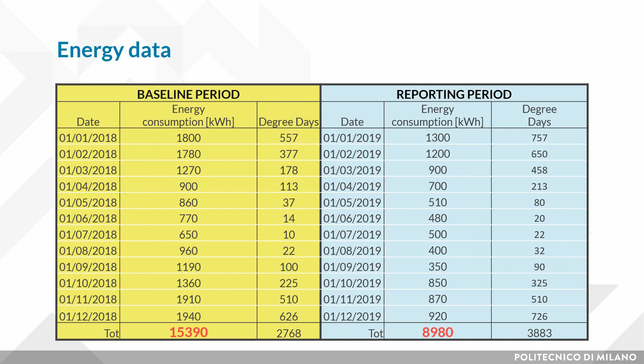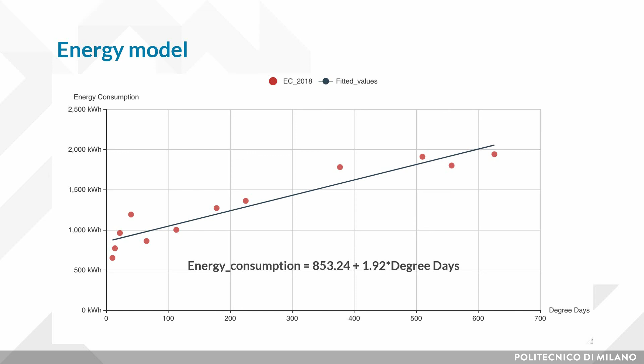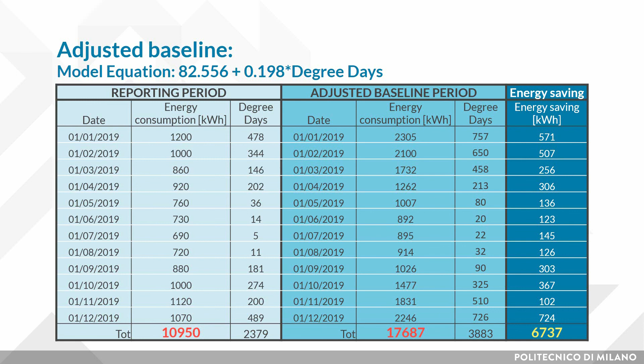To calculate the real savings, it is necessary to take into account independent variables such as the degree days. In this case, a simple model can be generated using a linear regression. The result is an equation that correlates the energy consumption of 2018 with degree days in the same year. The adjusted baseline period can now be calculated using the model equation with the value of degree days of 2019. The result is an estimation of the energy consumption that would have occurred if no improvement actions had been applied on the building. Now it's possible to calculate the real savings achieved.